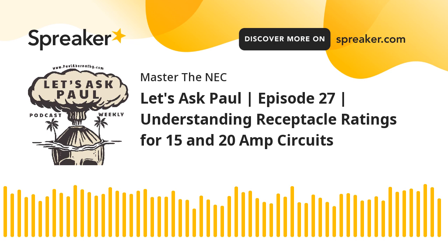And it should be, right? 20 amp circuit, 20 amp rated device, everything should be good. The next one: a 15 amp rated circuit breaker. Can I use a 20 amp single receptacle? Now remember, we couldn't use a 20 amp duplex on a 15, but here we can put a 20 amp single on a 15 amp. Why? Because 210.21(B)(1) says that the device cannot be less than the rating of the branch circuit. Well, the 20 amp rated single device is greater than the 15 amp branch circuit, keeping in mind that you're still going to limit your load to the 15 amps. Okay, so it is okay.